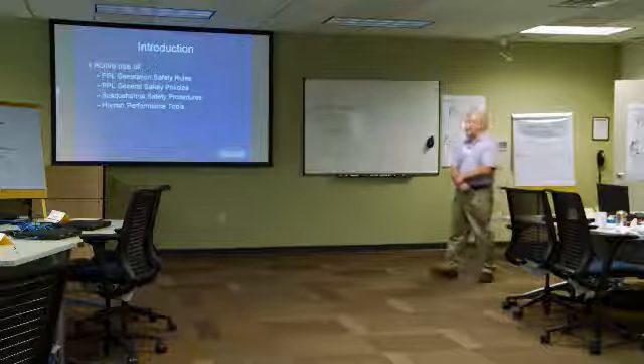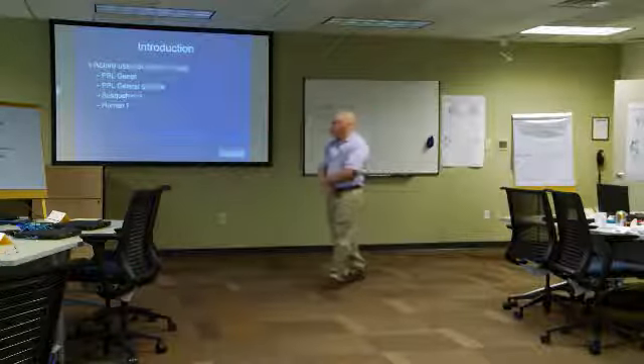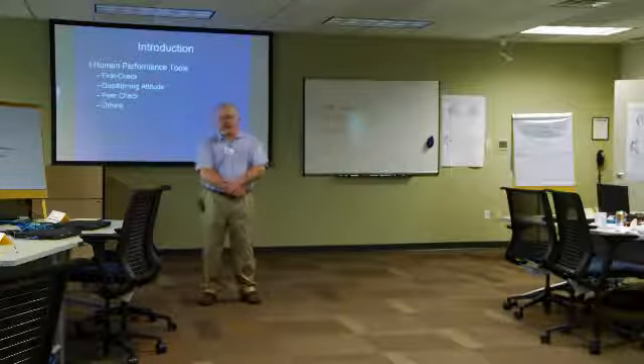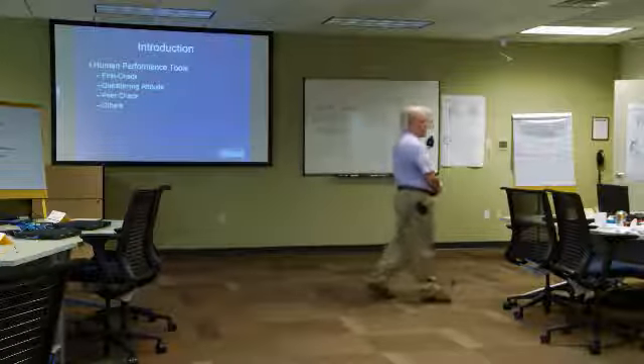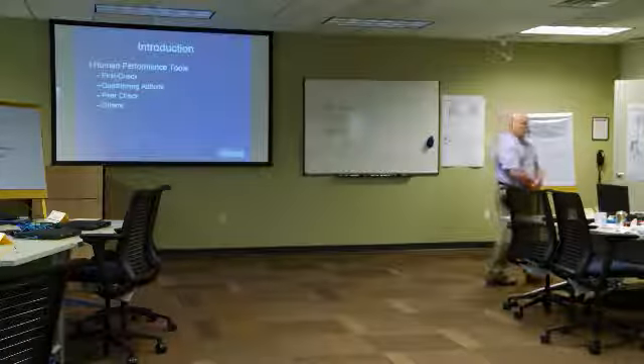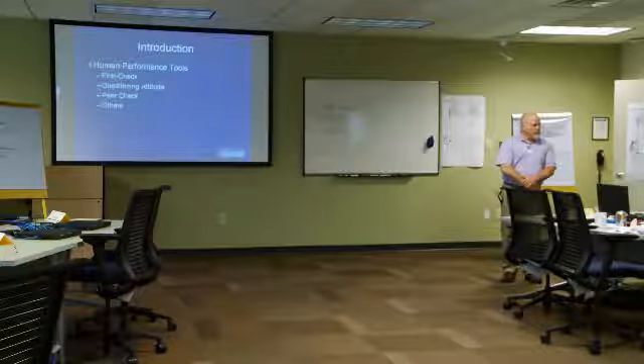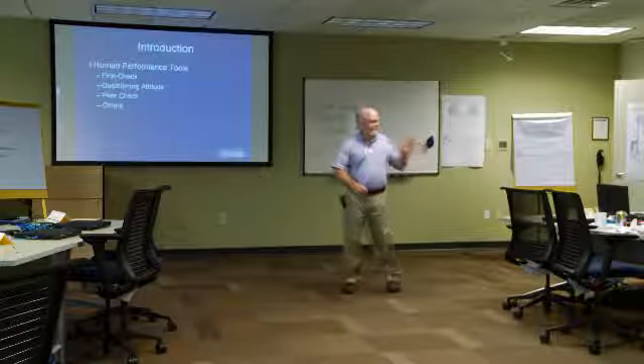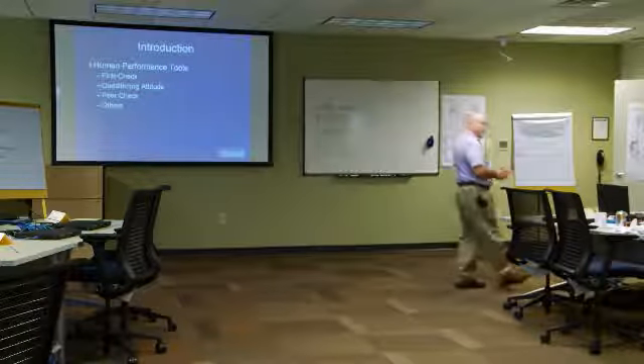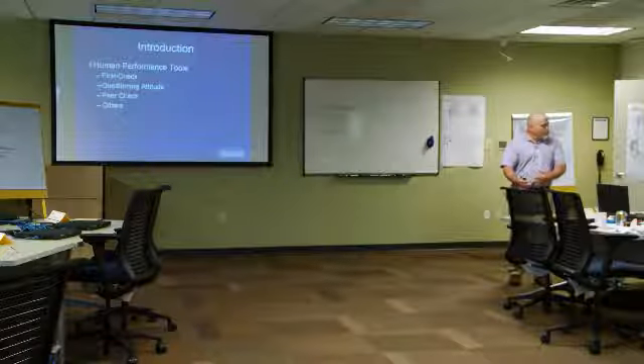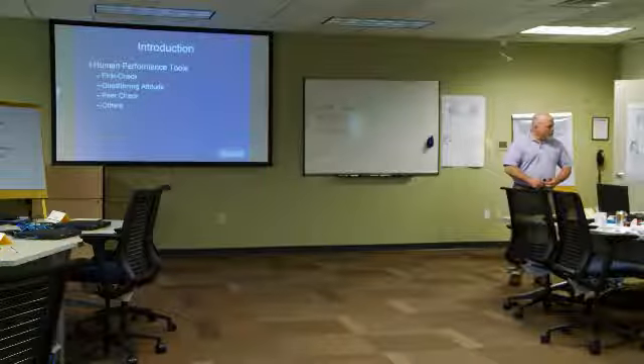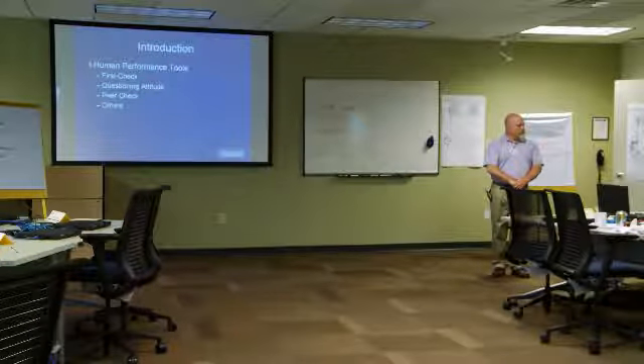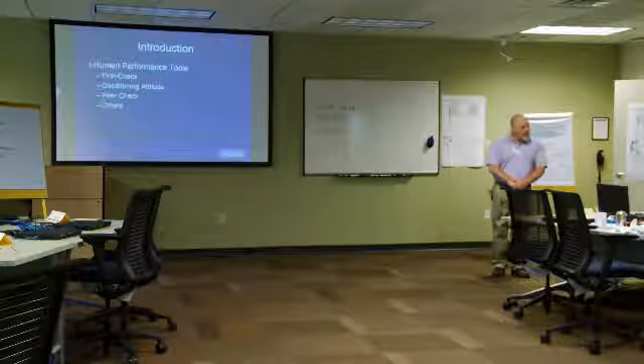Another thing we want to talk about throughout all this is the use of human performance tools. I wrote down a couple human performance tools that I felt could be used when we're applying temporary safety grounds. What does first check mean to you, John? Well, that would be the first time you check the condition of the equipment and see if it's de-energized or needs to be de-energized. So, Joe mentioned something very specific there. First check. The equipment is de-energized. So even before you want to check the equipment to de-energize, maybe what's one thing you want to check before you do that? Eric? You want to check that the equipment you're working on is the right equipment. If you're checking the EPN and then where I've come from a first check, when you check the EPN, you identify the equipment, and then you would call your supervisor or the control room and say, hey, I'm working on this. Exactly.